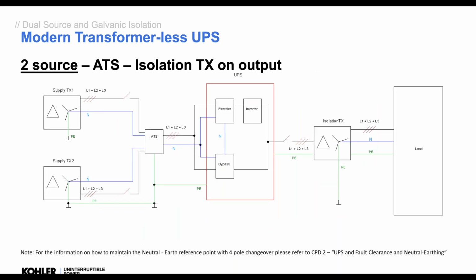Okay, we are seeing lots of designs where people say the UPS must be fed from two supplies, and then we're feeding the medical IT from two different UPSs, and then we value engineer it and say, well, no, we just feed the single UPS from a single source, but each UPS is fed from a different PES. Okay, but an alternative, if you want to have the UPS with two supplies, is to use an ATS on the input. Okay, so put an ATS here from the two different supplies. Lots of advantages to doing this. A, you don't need a transformer, and B, what a lot of people don't realize is, if you lose one supply to the rectifier, a lot of people think it will transfer to the bypass, but it doesn't.